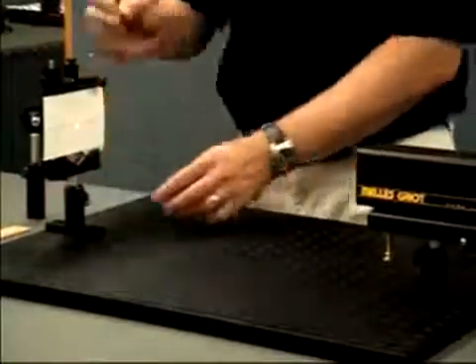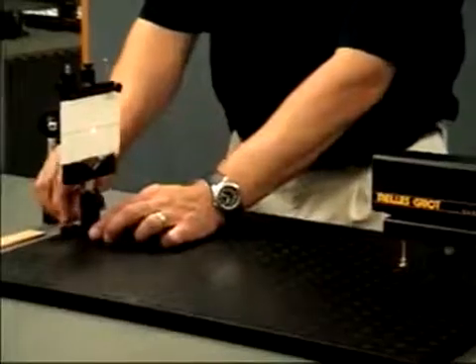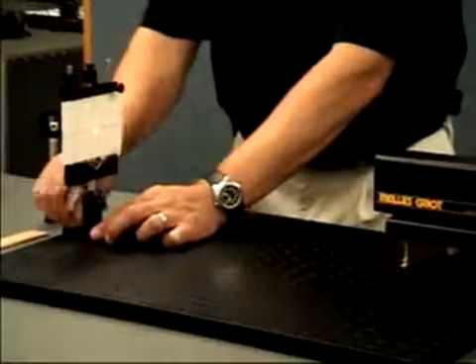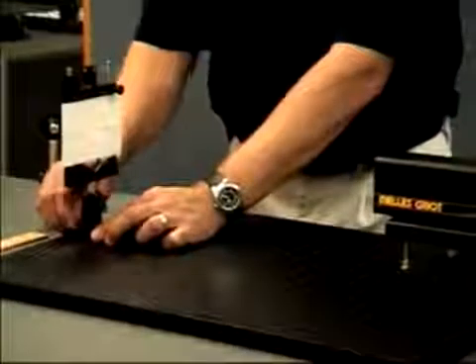And just to secure that target, I'm going to take a quarter-twenty set screw and tighten this down because we're going to use this target as we're doing the auto-collimation process.